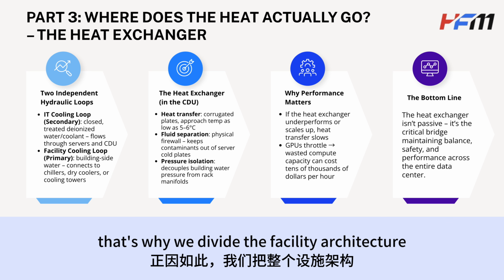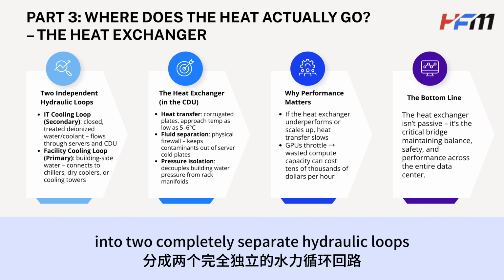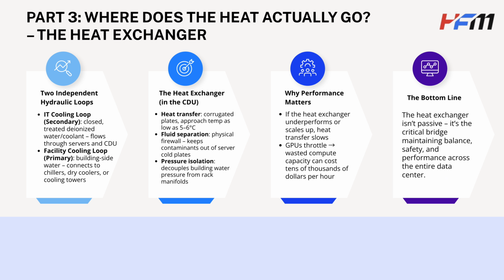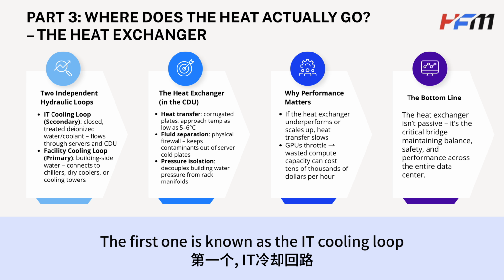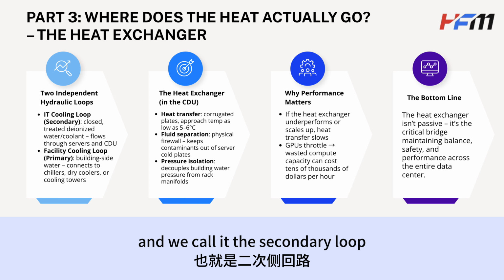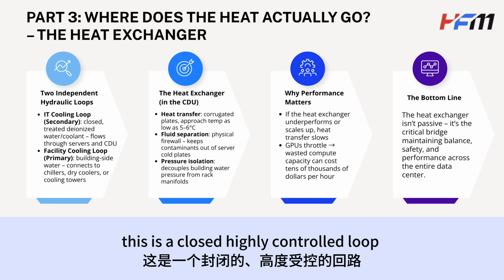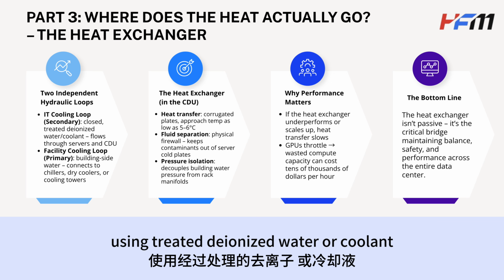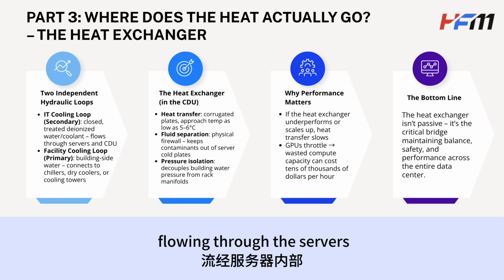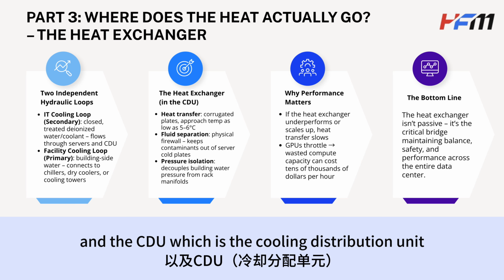Absolutely not. That's why we divide the facility architecture into 2 completely separate hydraulic loops. The first is known as the IT cooling loop, or secondary loop. This is a closed, highly controlled loop using treated deionized water or coolant flowing through the servers and the CDU, which is the cooling distribution unit.